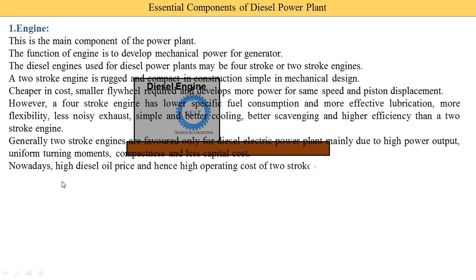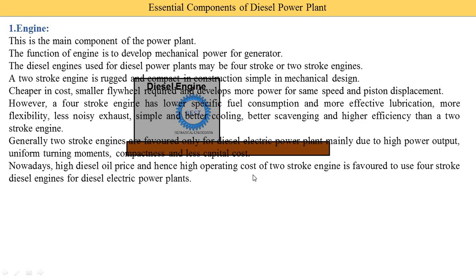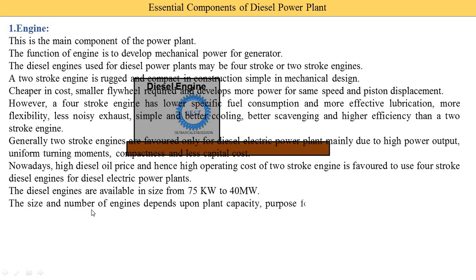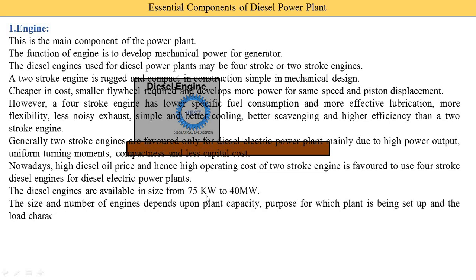Generally, two-stroke engines are favored only for diesel electric power plants mainly due to high power output, uniform turning moments, compactness, and less capital cost. Nowadays, due to high diesel prices meaning high operating cost, it is favored to use four-stroke diesel engines. Diesel engines are available in sizes from 75 kilowatt to 40 megawatt. The size and number of engines depends on the plant capacity, the purpose for which the plant is set up, and the load characteristics.